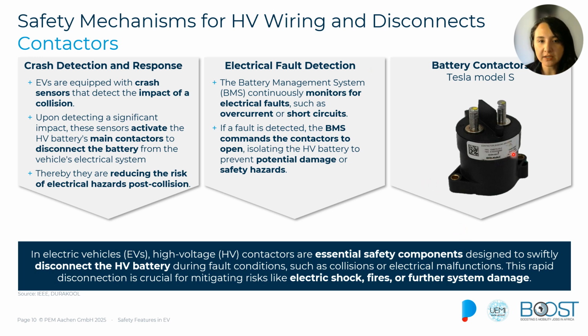Also, these contactors will be opened based on the decisions of our battery management system and based on electrical fault detections. So the battery management system is going to be monitoring all the electrical conditions and thermal conditions of the battery, like overcurrent, over voltages, short circuits, and other faults. And on the detection of any of these, it will command the contactors to open, stopping the current flow and limiting the damage to the system.